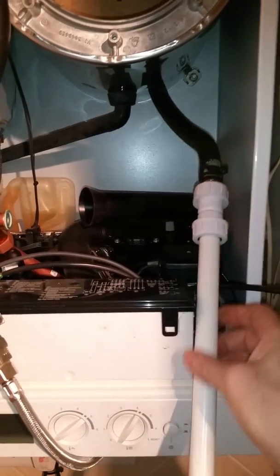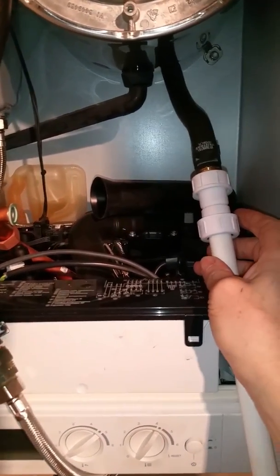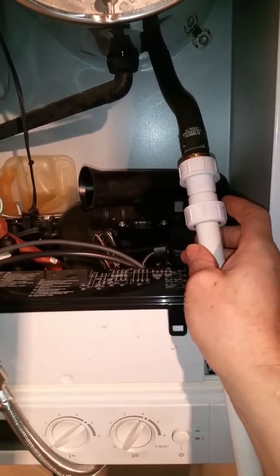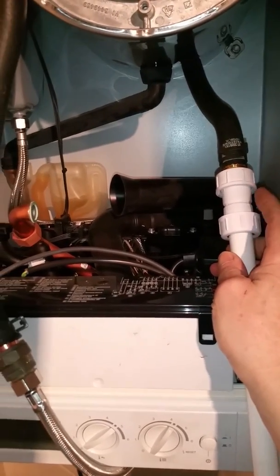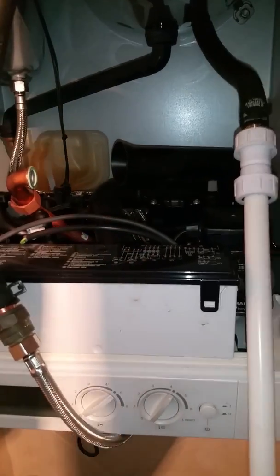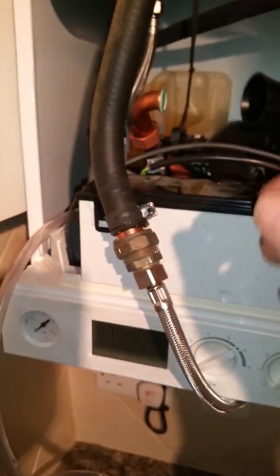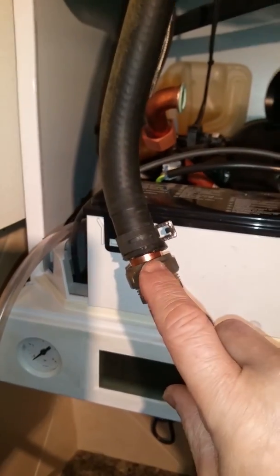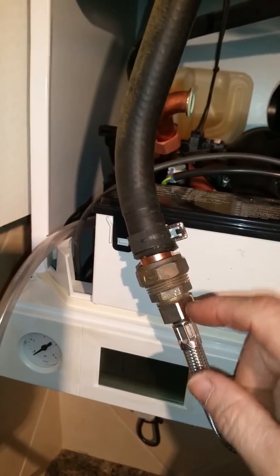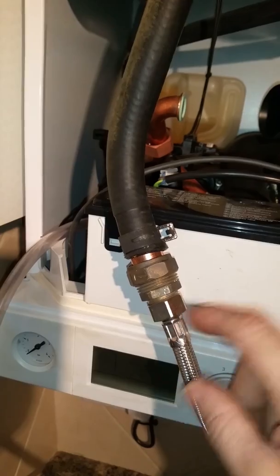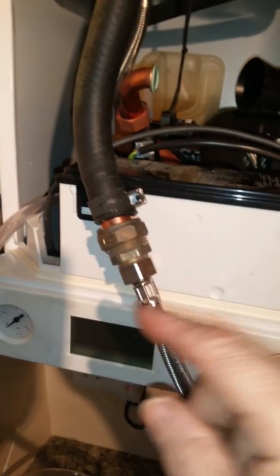So what I found was that I've got an overflow compression straight connector, which is malleable enough to fit onto 22mm. I've extended that hose from the point it comes out of the heat exchanger into a bucket. Here I've got a 22 to 15mm socket reducer, onto a compression 22mm to 1/2 inch iron, and a standard 1/2 inch connector onto the filling loop in the boiler.